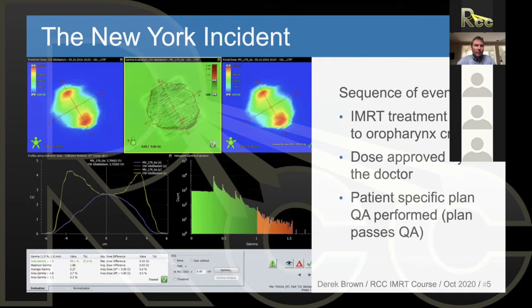There are lots of different ways of doing patient-specific IMRT QA. The image I'm showing on the left is a Varian solution called portal dosimetry. Essentially we're delivering that IMRT beam on the LINAC without the patient and measuring what is happening, then comparing that to what we expect to happen. If everything works out, we say this is good and move forward to treat our patient.